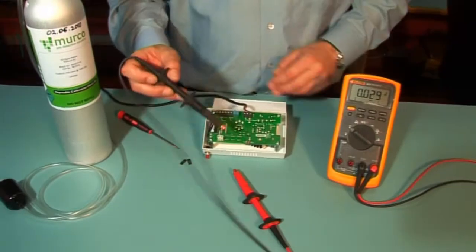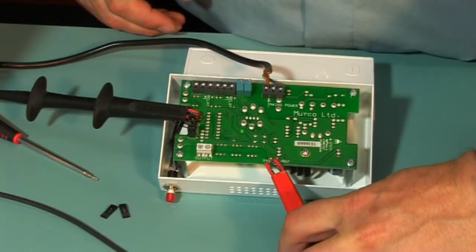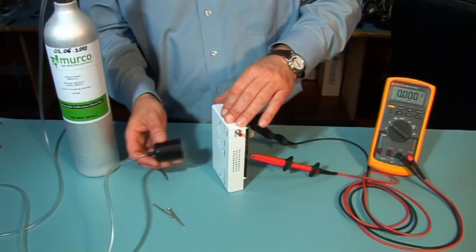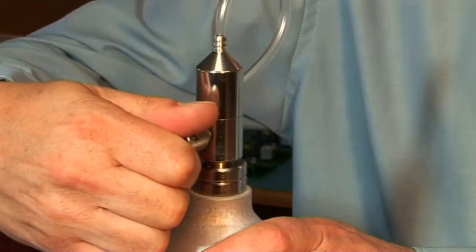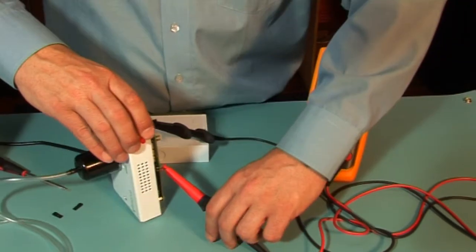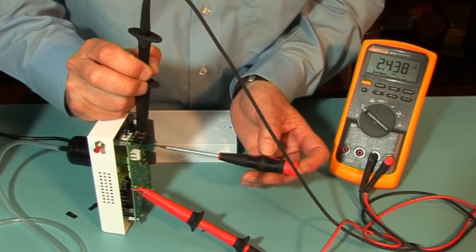Having carried out the electrical setup, connect the voltmeter between V0 and Vs with your known target gas and desired range. Expose the sensor to the gas and allow the standby voltage to climb. Once the voltage stops climbing and stabilizes, then that voltage is the alarm voltage and should be recorded. Record this value and then between V0 and Vref, adjust P2 to approximately 50 millivolts below this voltage.